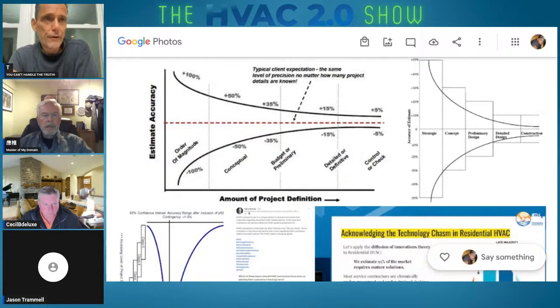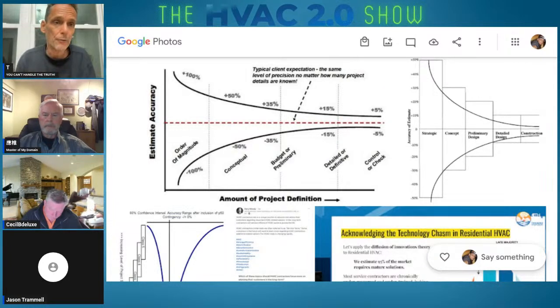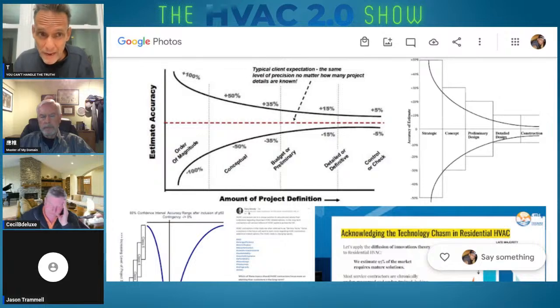So what I've heard from Ronnie and Austin is that, from the duct analysis service that they used to provide, as kind of a warranty service, or as a service to help people decide what their next steps are to fix problems with their house, they would often adjust the size of the ductwork without regard to the load of the house. It's now prioritized: we're adjusting the ductwork to match the equipment without recognizing that the equipment's wrong for the load of the house. They were having homeowner problems that didn't get resolved after changing ductwork.